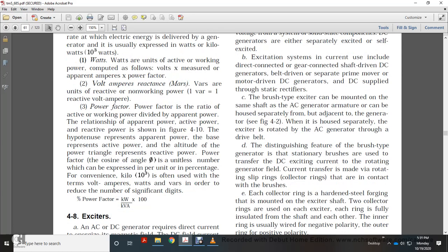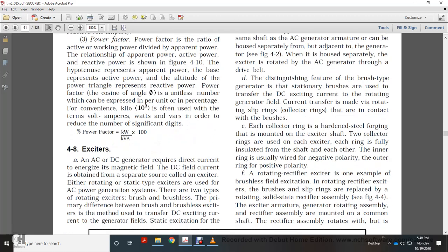Power factor is the ratio of active, working power to apparent power, the relation of the apparent power with the active power and the reactive power shown in figure 4.10. The hypotenuse represents the apparent power, the base represents the active power, and the altitude of the power triangle represents the reactive power. The power factor is the cosine of the angle theta, a unitless number which can be expressed per unit or as a percentage. For convenience, kilo, 10 to the third, is often used with the terms volt-amps and watts, and kilovolt-amps, in order to reduce the number of significant digits. Percentage power factor equals kilowatts over kilovolt-amperes times 100.